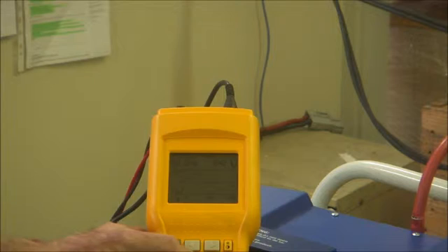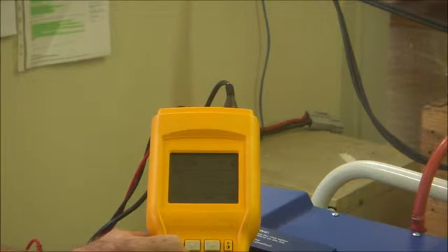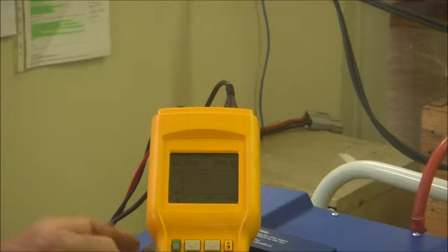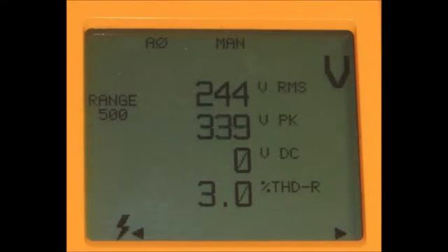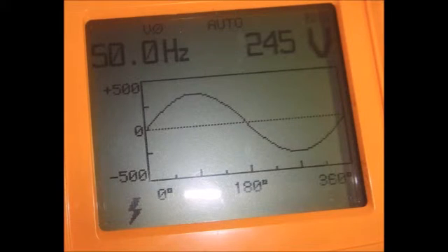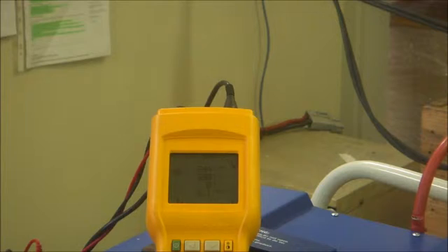Okay, let's have a look and see what we've got. We've got about 6.8 amps, about 1.67 kilowatts, and about 240 volts. Let's have a look at the harmonic distortion. It's 3.1%. That's good. That's about as good as you get out of your power point. Now, let's increase the load further.